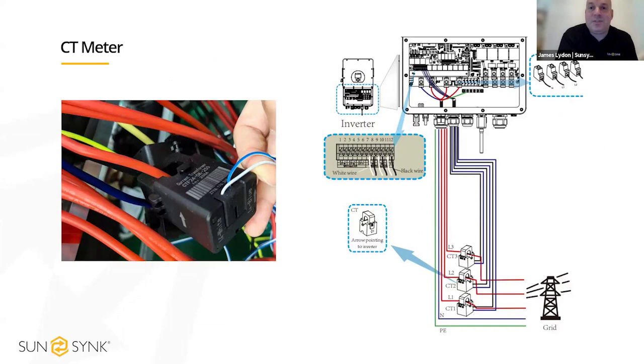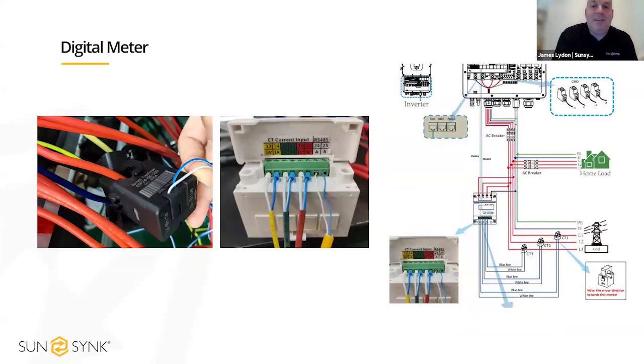Okay, so in all of the boxes for our hybrid inverters, the CT coils are included as standard. So if it's a single phase unit, you'll have 1 CT, and obviously if it's a 3-phase unit, you'll have 3 CT coils in the box as standard. The length of the cable that they come with is about 6 meters. There are a lot of occasions where the main incomer is further than 6 meters. So what we recommend, on some of the single phase units, if you need to extend the CT, is that you're good to extend it with a twisted pair up to maybe 15 meters, let's say.